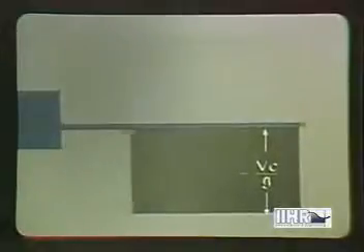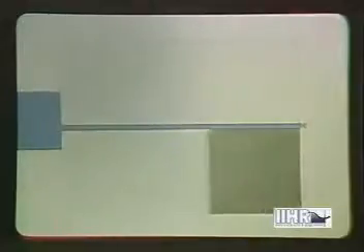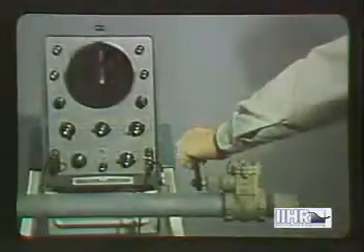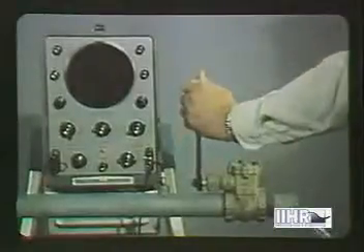As was shown in the first film, the sudden closure of a valve at the end of a long pipe causes an elastic surge to be propagated back and forth between valve and reservoir at sonic speed. At the reservoir end of the pipe, it is always reflected negatively, and at the valve end, it is always reflected positively, as a result of which the pressure fluctuates rapidly between positive and negative values, the waveform being influenced also by the elasticity and resistance of the pipe.